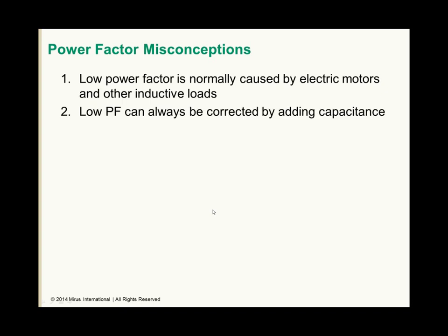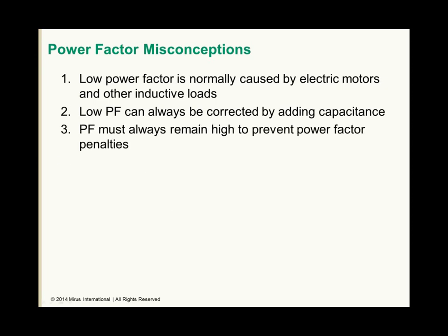The second one is low power factor can always be corrected by adding capacitance. If low power factor is due to harmonics, treating with capacitors can often make the problem worse. Third is power factor must always remain high to prevent power factor penalties. Although there are many different ways that power factor penalties are applied by utilities throughout the world, they almost universally apply these penalties during periods of peak demand. Therefore, if low power factor only occurs under lightly loaded conditions, it will not result in power factor penalties.